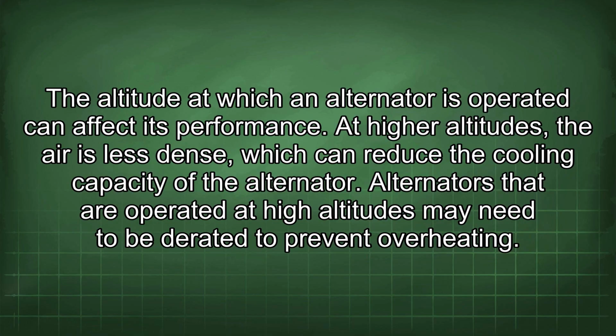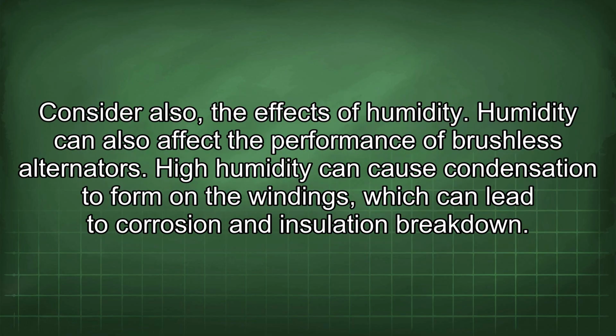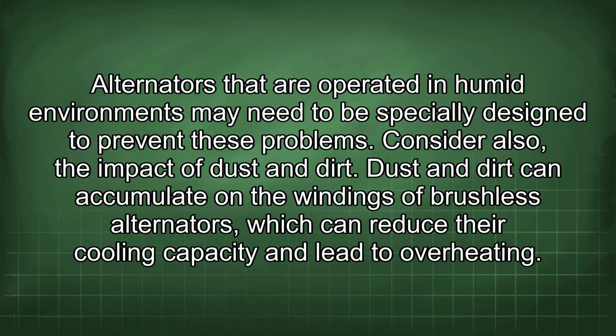The altitude at which an alternator is operated can affect its performance. At higher altitudes, the air is less dense, which can reduce the cooling capacity of the alternator. Alternators that are operated at high altitudes may need to be derated to prevent overheating. Consider also the effects of humidity. Humidity can also affect the performance of brushless alternators. High humidity can cause condensation to form on the windings, which can lead to corrosion and insulation breakdown. Alternators that are operated in humid environments may need to be specially designed to prevent these problems.